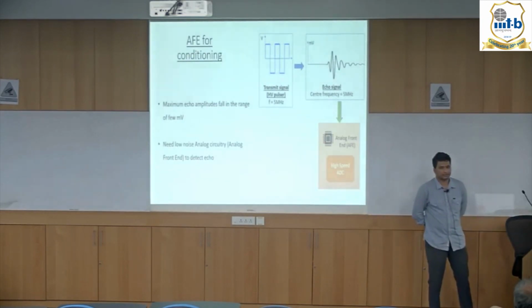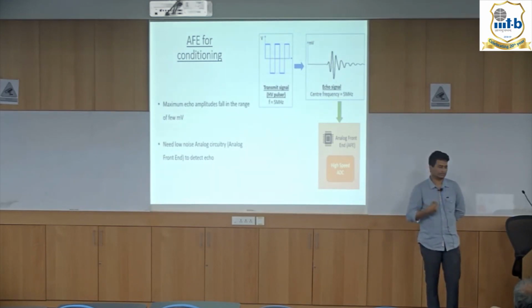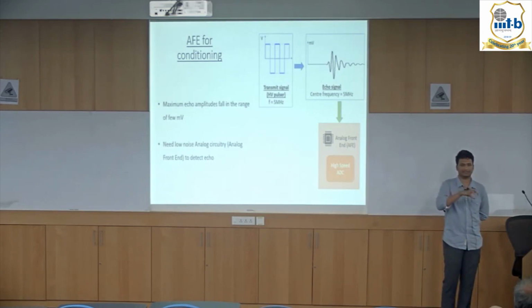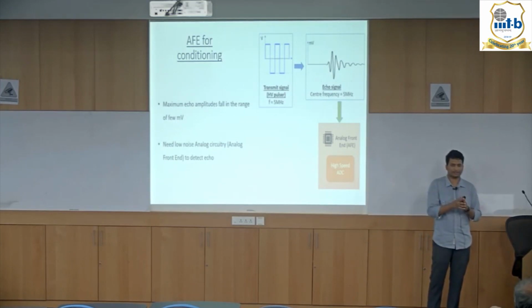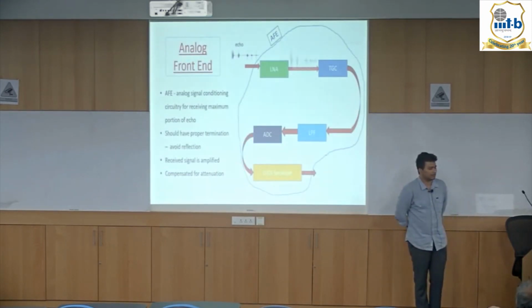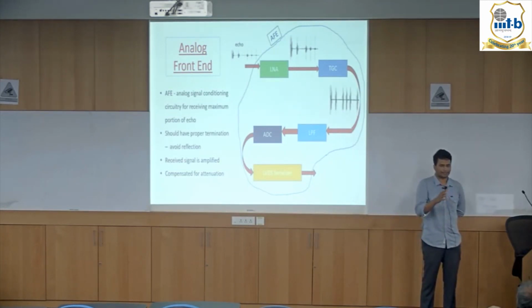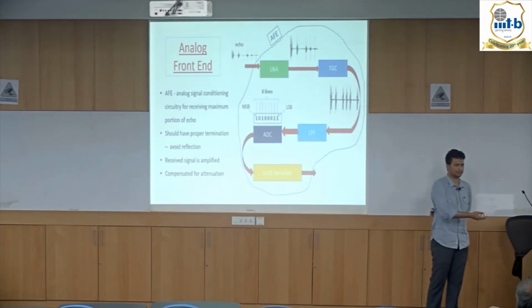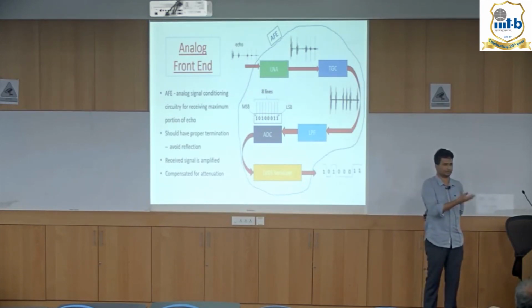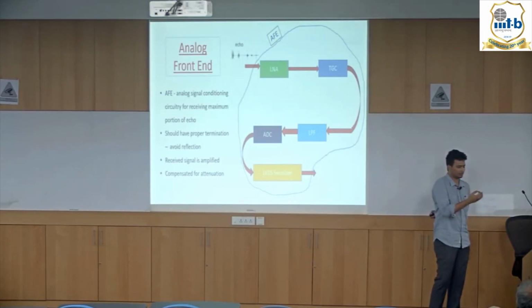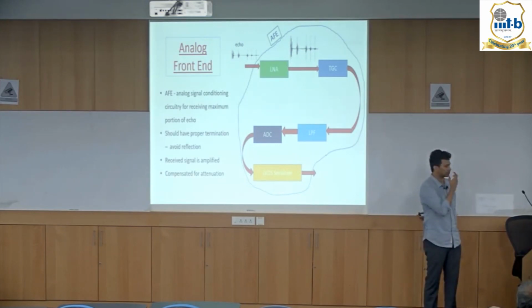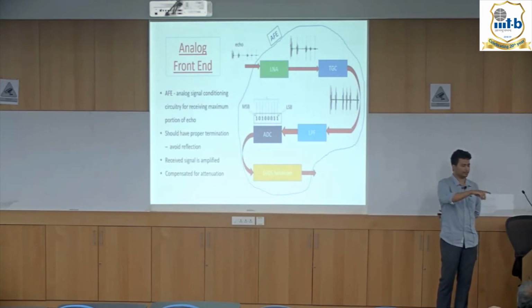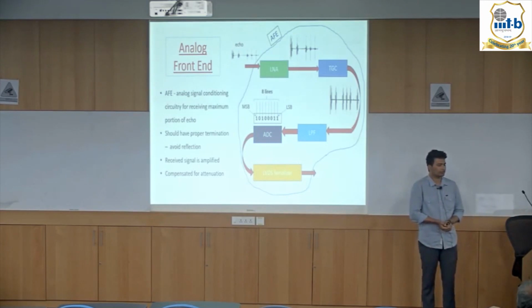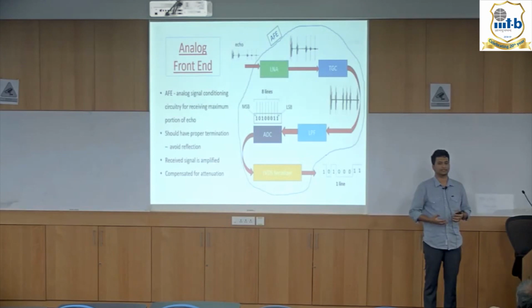As already mentioned, the strength of the echo is extremely low. So we use something called an analog front end, which is specialized for receiving low voltage signals. This analog front end is a system which involves several subsystems of circuitry. The first one is the LNA, the low noise amplifier. It is a simple amplifier, but it adds very low noise to the signal. All electronic systems have noise within them, which they add to the signal that has been received. So a low noise amplifier is used since the echo is of very low strength, and then a TGC circuit will normalize the echo signal, and then it goes through an anti-aliasing filter so that it can be converted into digital data through an ADC.